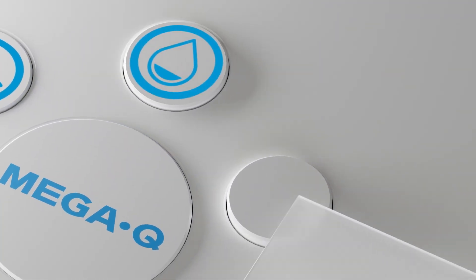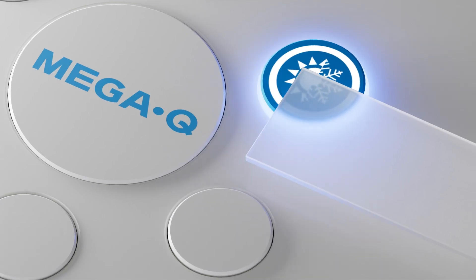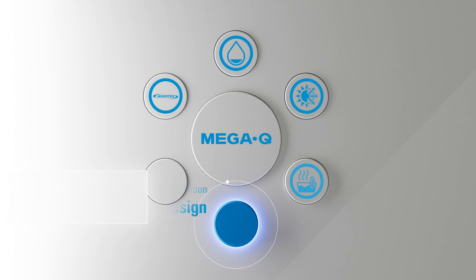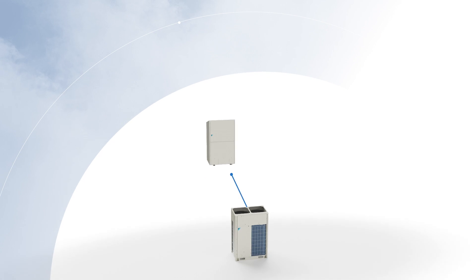MegaQ provides reliable year-round hot water generation at ambient temperatures from minus 4 degrees Fahrenheit to 109 degrees Fahrenheit. The system can generate customizable high leaving water temperatures from 140 degrees Fahrenheit to 194 degrees Fahrenheit, with inlet water temperatures from 41 degrees Fahrenheit to 176 degrees Fahrenheit. The flexible system design allows for vertical separation of up to 65 feet between the heat source unit and the cascade unit, offering flexible application design and ease of service.